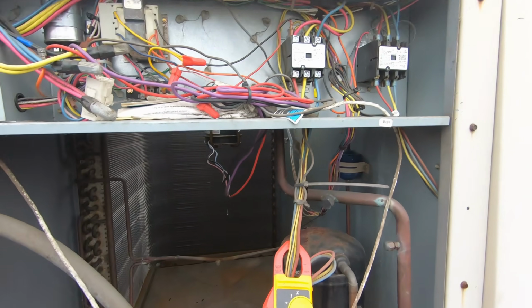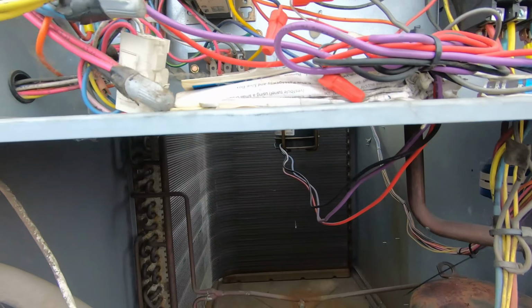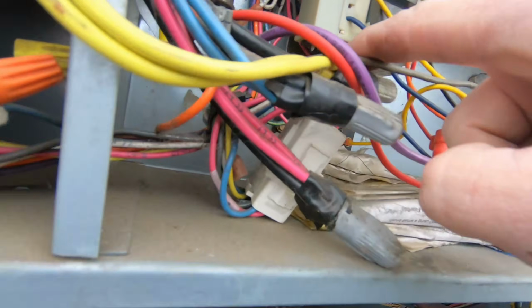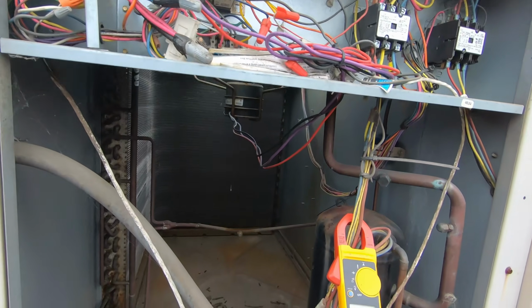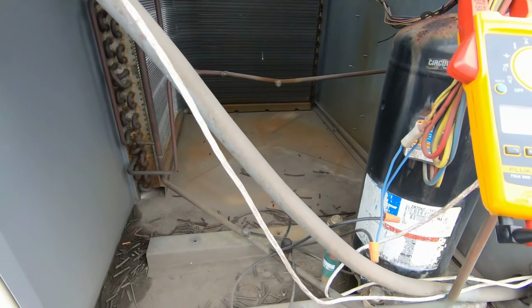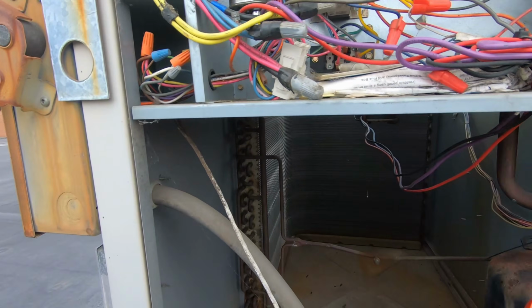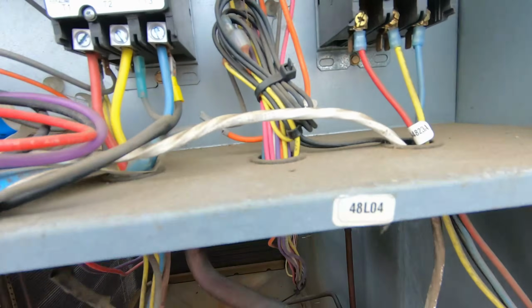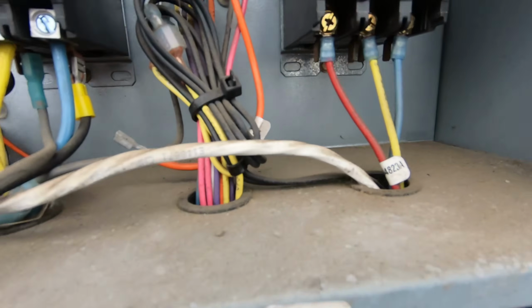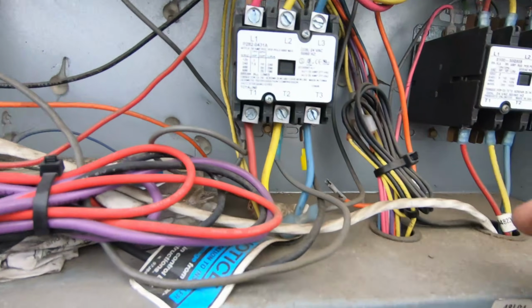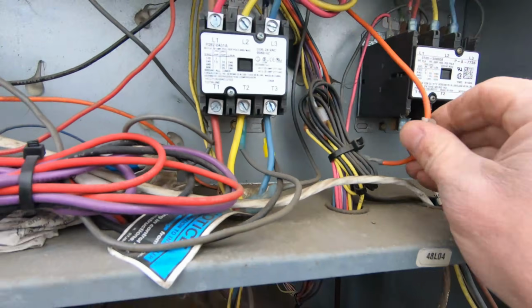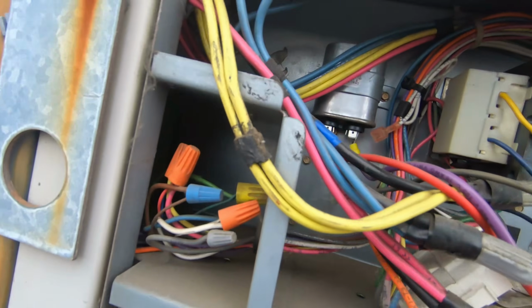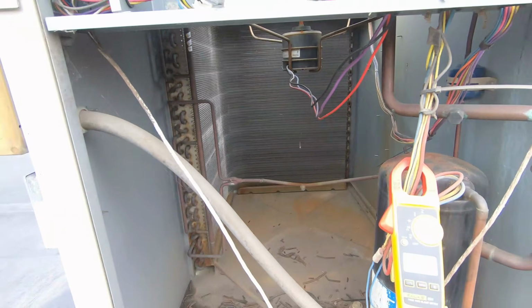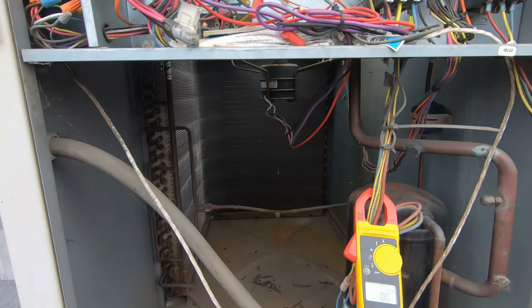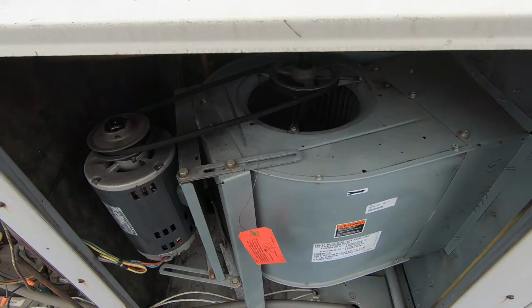All right, guys, I got 208 here at the contactor, but I can see back here our little 3 amp fuse on the transformer is tripped. So I'm gonna look everything over. I'm gonna kick this power off real quick, look everything over and see if I can find any obvious signs. We've got some wires pulled here. Let's see here, I got an orange one there and I got an orange one here. I wonder if that's the same wire. I'm gonna test continuity across that and see if somebody pulled or replaced a wire.